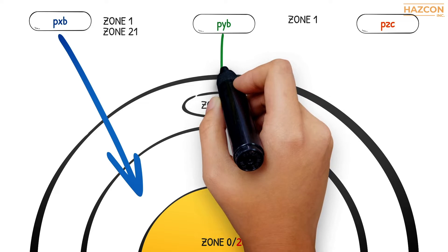Protection by pressurization is subdivided in the standard into three levels of protection called PXB, PYB, and PZC. PXB enables uncertified equipment to be installed in a Zone 1 or Zone 21 location. PYB enables equipment suitable for Zone 2 to be installed in a Zone 1 gas explosive area.